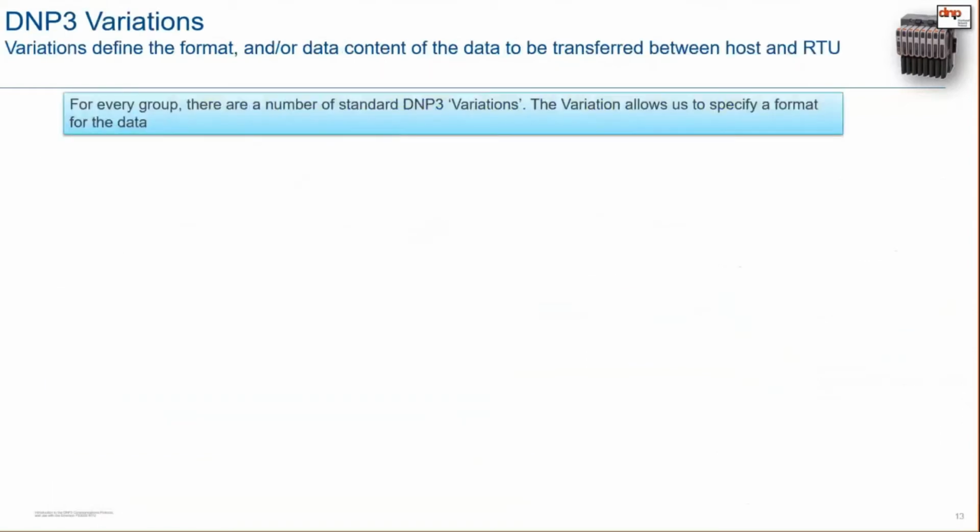One thing I've not discussed, but anyone who's familiar with Modbus is familiar with, is that Modbus has many different ways of representing values. So, for example, you might have a floating point, you might have an integer, a signed integer, a 64-bit integer, and then there's a lot of complications with the different order of bytes and so on. And every Modbus communication setup I've ever done, we've had problems with them, especially from different manufacturers, because there's no real standard. DNP3 has a huge advantage.